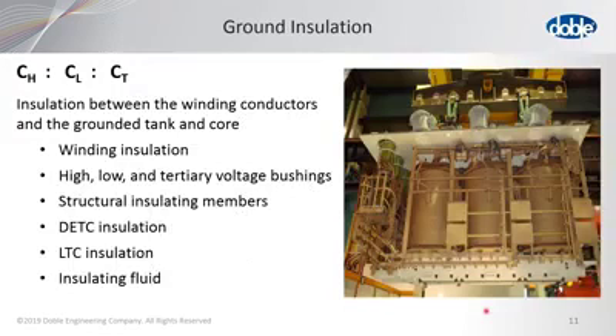Now, it's also very good to get a good feeling of what is inside the tank while you're doing the tests, so that you can identify if there's an issue anywhere in your testing. So the insulation between the winding conductors and the grounded tank and core are included here. Now you can have the winding insulation that is just around the windings, the low, tertiary, and high voltage bushings. Now this is the turret for the high voltage. And notice the bushings are not installed, but they would be included in the test during the overall test.